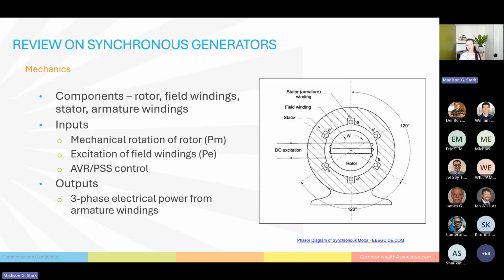So you have two major inputs as well as a control input to the synchronous generator. You have the mechanical rotation of the rotor. So this rotor is attached to a turbine. And there is some mechanical force exerted on the turbine that is causing it to spin. And that spinning of the turbine, which is coupled with the rotor, is then forcing the rotor to spin.